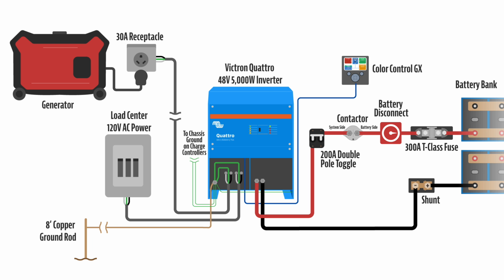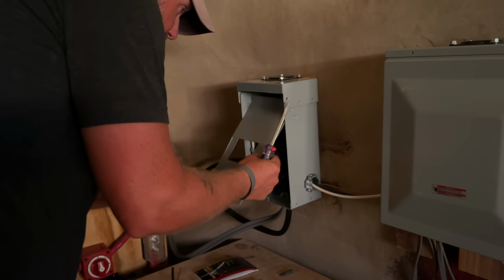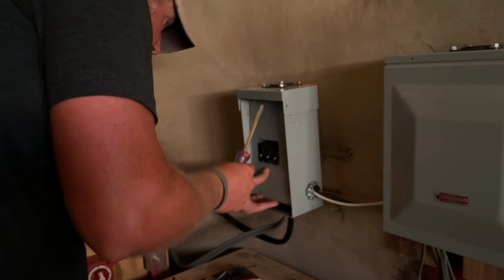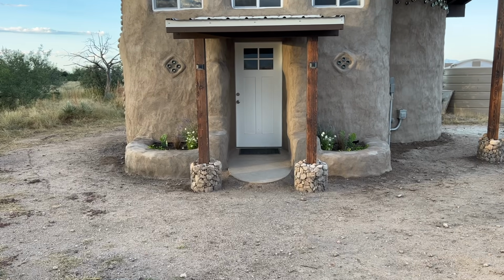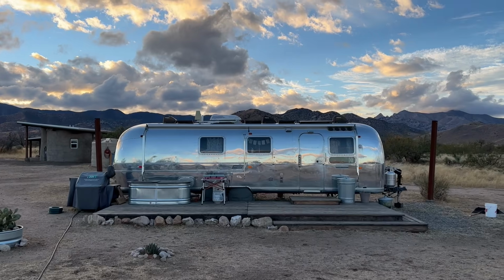Finally, we get to the whole point of this setup: clean, stable 120 volt power. This is as simple as running a Romex cable from the AC out into a circuit breaker box, or however you need to connect your setup. In our case, we ran to a main lug panel which separates the power into 3 connections: one for our house, one for this solar shed, and one for our Airstream. We also have another breaker box for all the elements inside the solar shed. Everyone's going to run their 120 or 220 volt differently, so we won't get into more detail there.